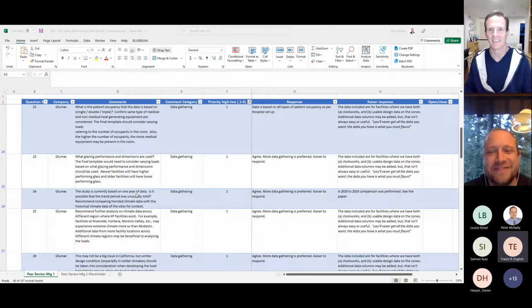But it gets all the way down to, at one site, we were dealing with a BAS system that just had a list of zone numbers with temperatures associated with them. It turned out on that project the controls installer didn't use the same zone numbers as the design engineer, who hadn't put zone numbers on the plans per se. The zone numbers actually came in through a controls submittal, so you could look at the record drawings and just wouldn't find them.